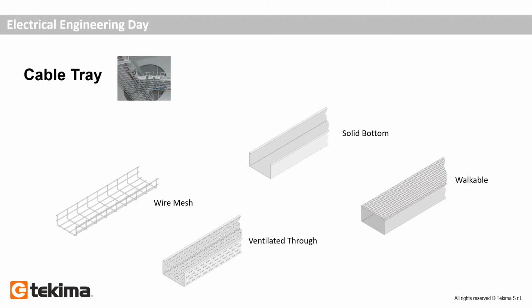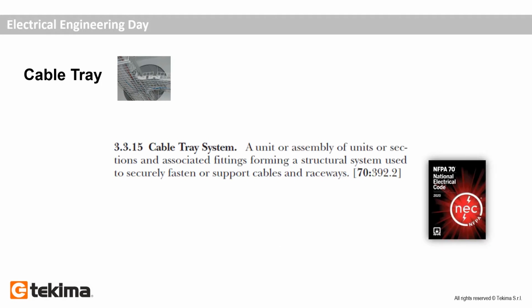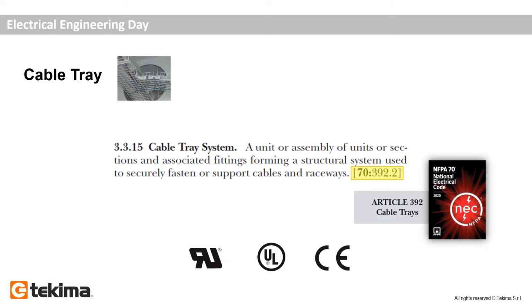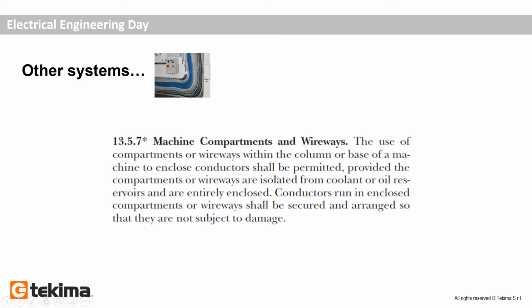It's very similar to what we usually apply in Europe. Wire mesh, solid bottom, walkable, ventilated trough. And again, in the standard, you can see that the products have to be listed. Recognized markings or CE mark are not allowed. Regarding the definition of other systems, they are considered exceptions, and anyway, the standard considers these systems as raceways.